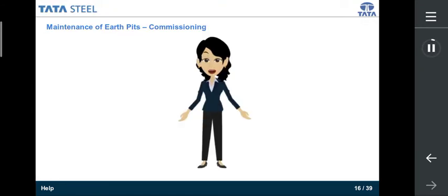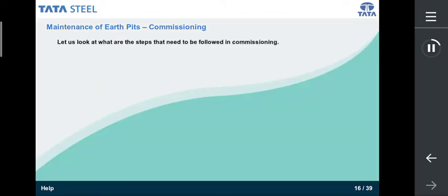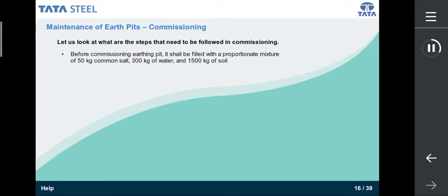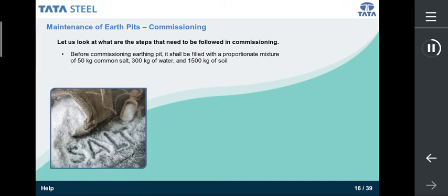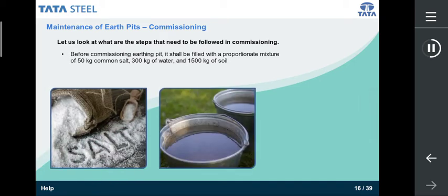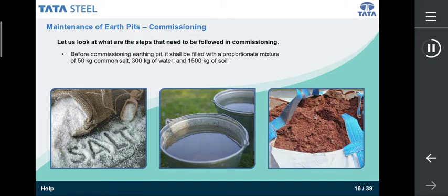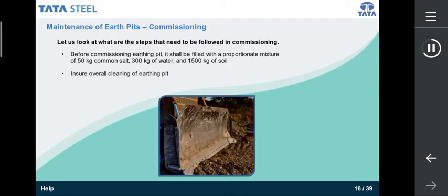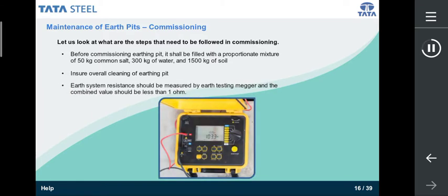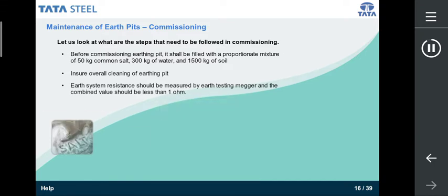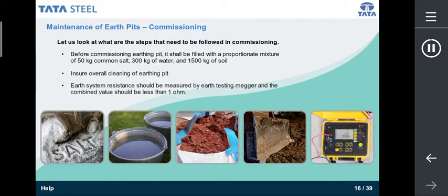In the process of maintenance of earth pits, the first step is commissioning. Let us look at what are the steps that need to be followed in commissioning. Before commissioning, earthing pits shall be filled with a proportionate mixture of 50 kg common salt, 300 kg of water, and 1500 kg of soil. Ensure overall cleaning of the earthing pit, and earth system resistance should be measured by an earth testing meter, and the combined value should be less than 1 ohm. Let us move on to the next step, that is inspection.